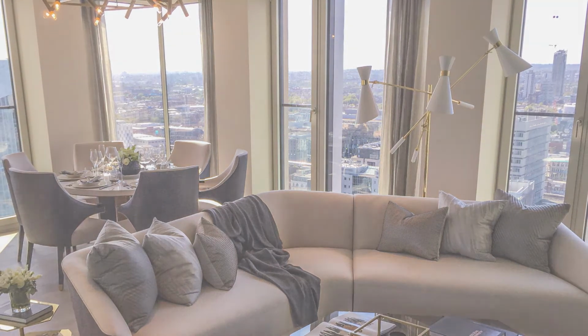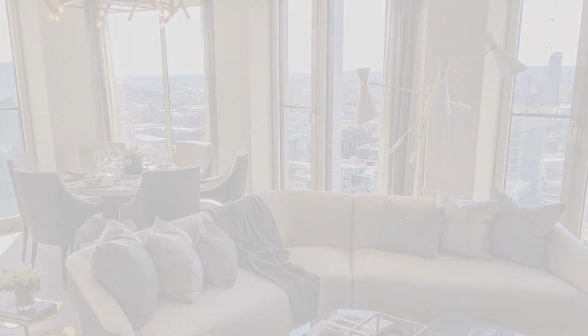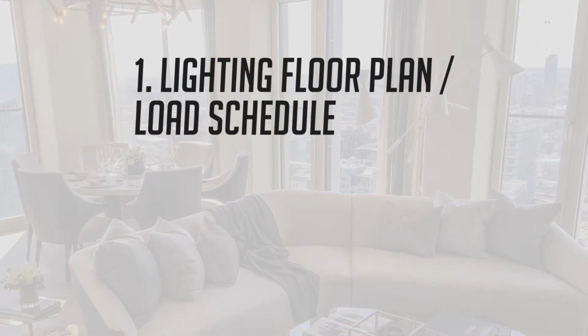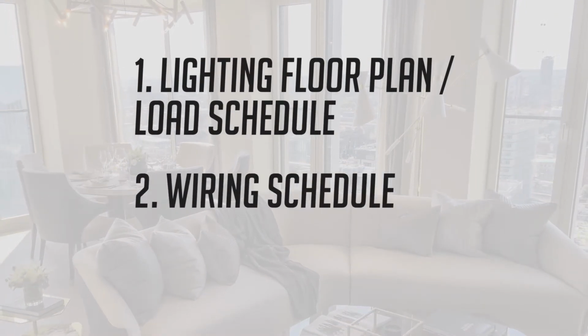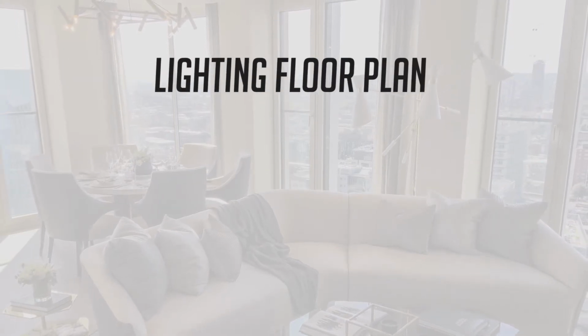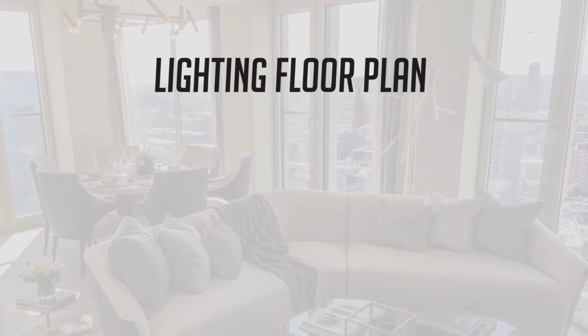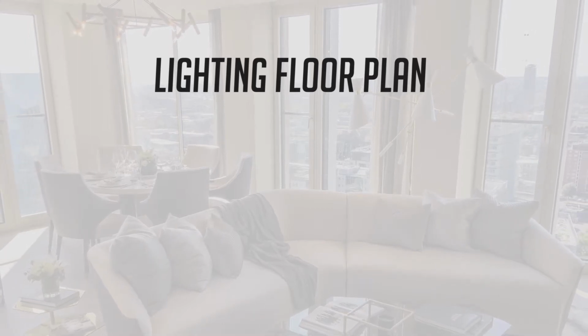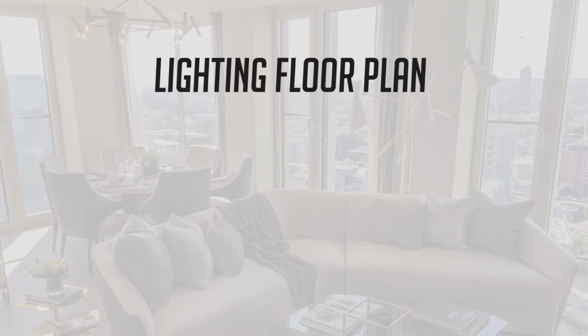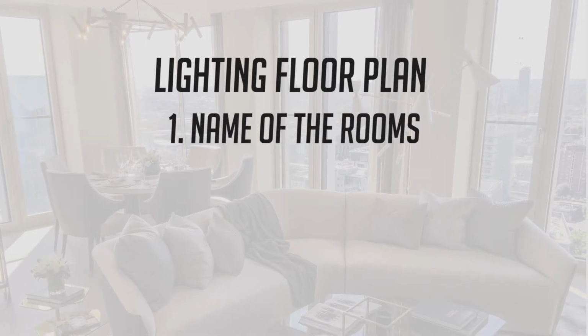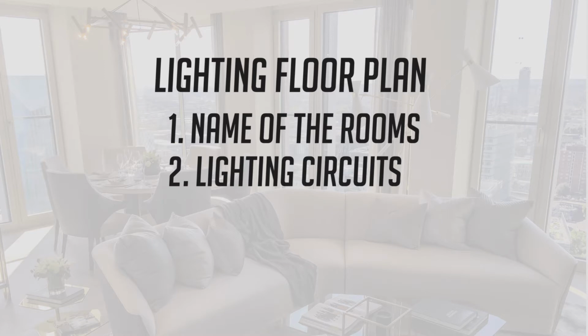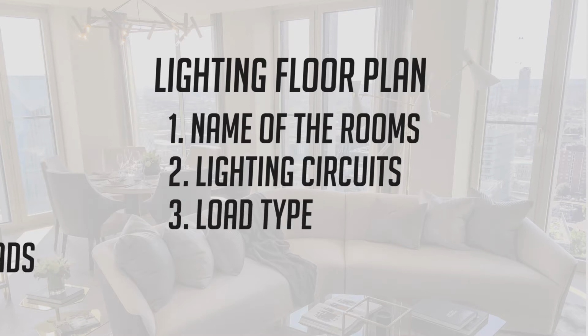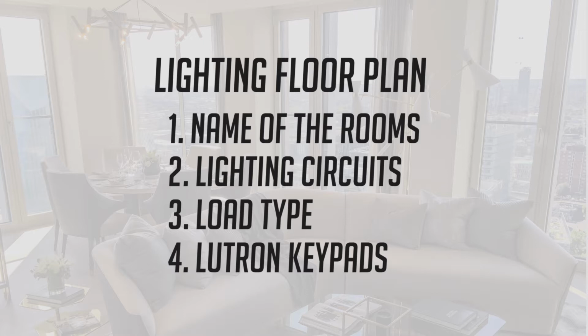Well, that's very easy. To start, you will need a lighting floor plan or a load schedule, as well as a wiring schedule. But let's start with the lighting floor plan, because there are different ways a lighting floor plan looks. And in your case, the most important pieces of information that you need to locate on your lighting floor plan are the name of the rooms, the lighting circuits, the load type for those lighting circuits, and the position and wiring of the Lutron keypads. So let's have a quick look at what this looks like on an actual floor plan.